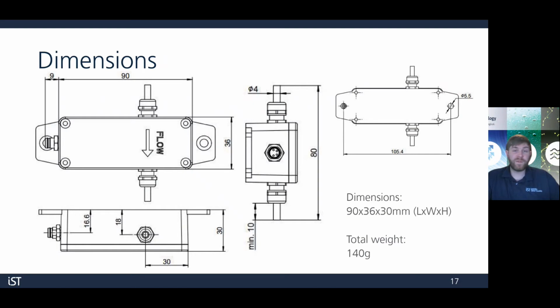Here we have a drawing of the module. The module is pretty lightweight, weighing in at just 140 grams and has a relatively small footprint. I have this one here, like I showed before. Here we have our flow inlet and the outlet, some mounting holes, and our connector here for our data output. So it works in many installation configurations, but we usually recommend having it horizontal like this, or if you want to install it with the tube going vertically, you want the arrow facing up and your flow going that way. That'll give you the best behavior and the best response.